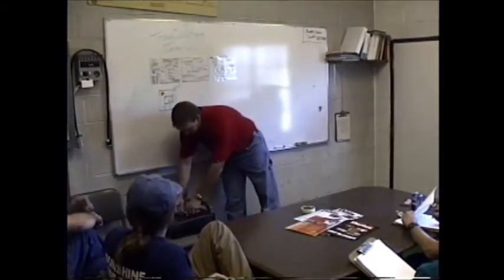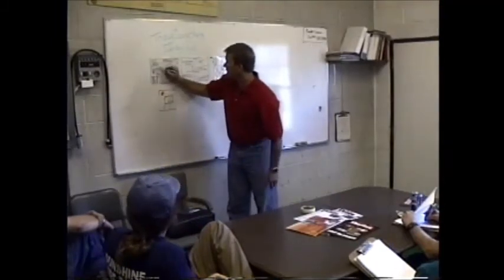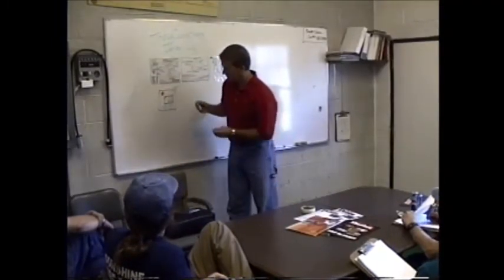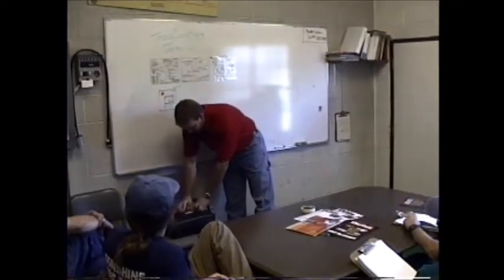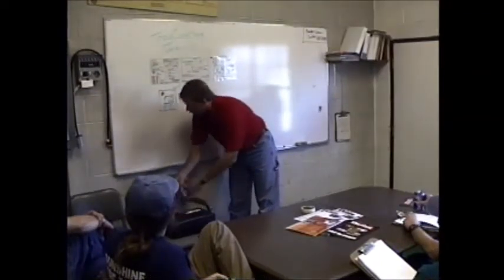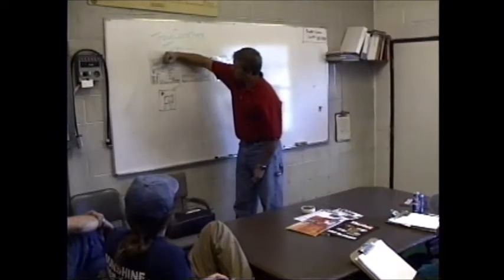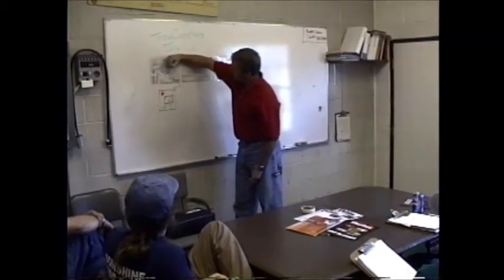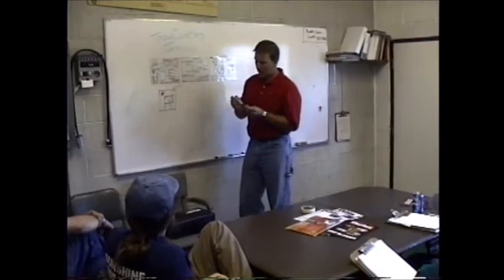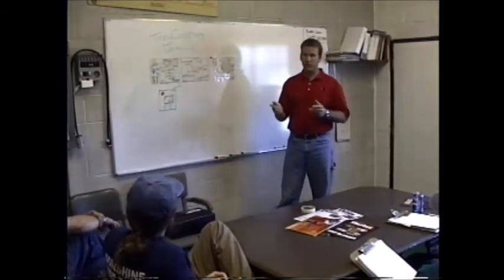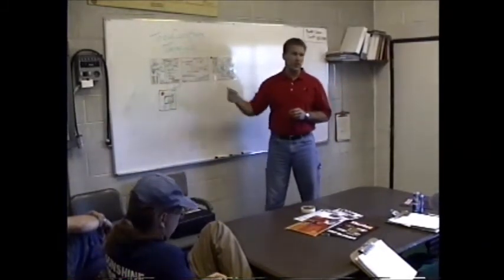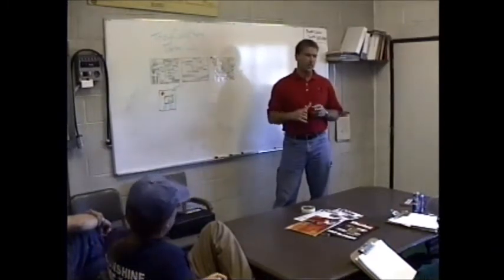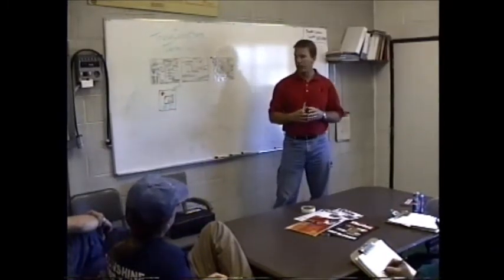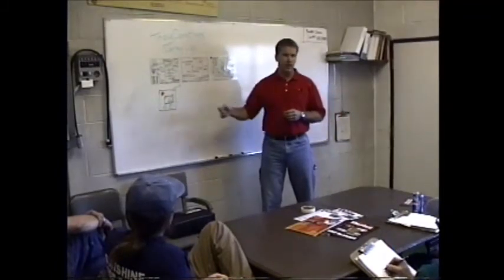And just to show by color here, we've got yellow foam coming from the foam tank, and then when that yellow foam hits the blue water, we're going to have a foam water solution that's then going to transport itself into all of these various outlets. It's going to fill up your entire manifold going to all these various lines. Okay, now we have foam water solution to all those lines. Just by pushing a red button, you've now made all of those lines foam. And they're all going to have the same exact mixture of foam to water ratio. And it's going to be whatever this device is set at.